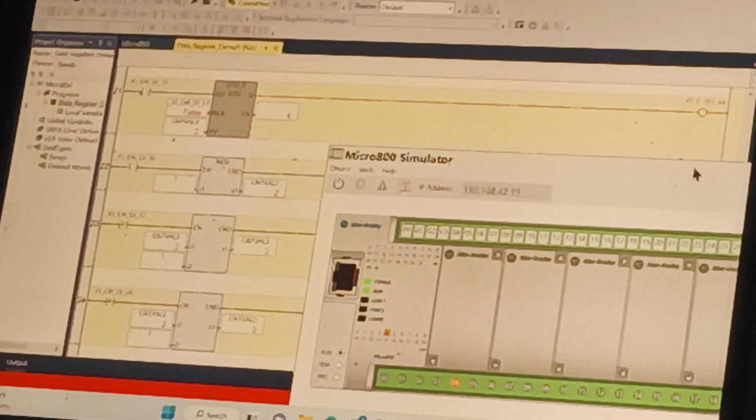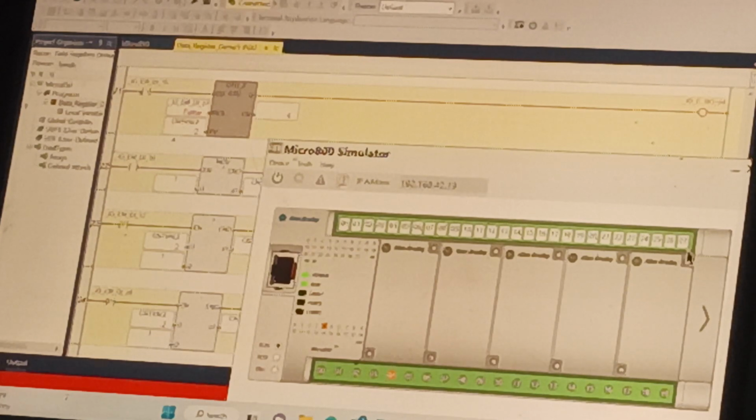So what we'll want to do is reset that. And now we don't have an output on Y because our count value is at 2, and we reset it to 0. So input 15 does the counting. 1, 2, and the reason why I didn't do anything is I left my reset on. That's why you want the reset to be on a momentary push button, not a toggle.